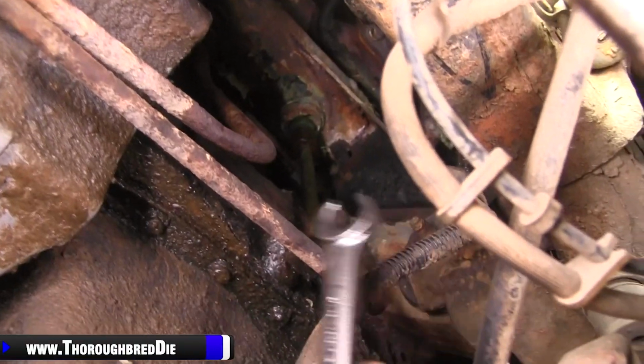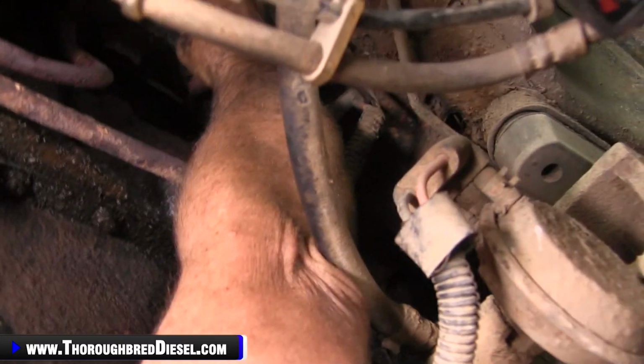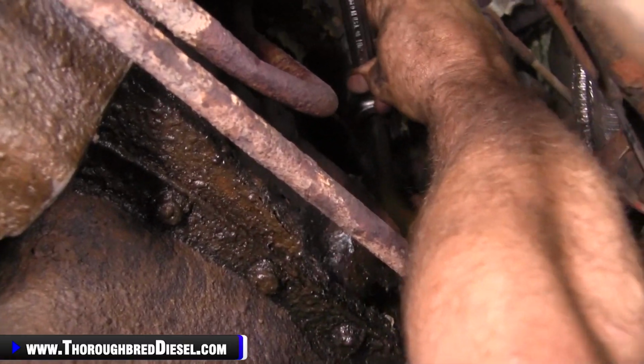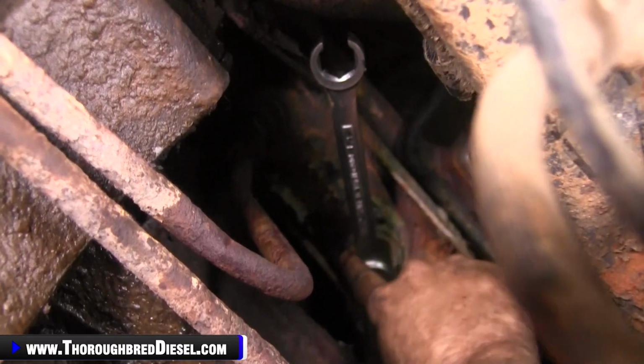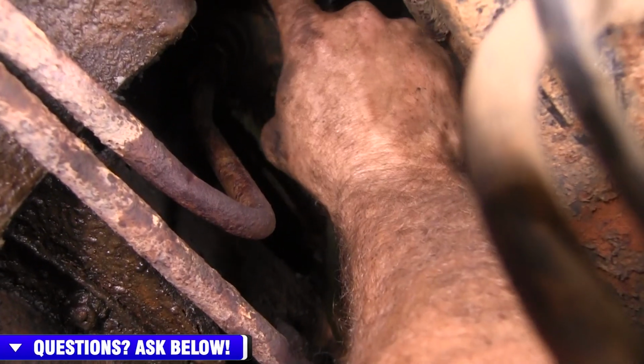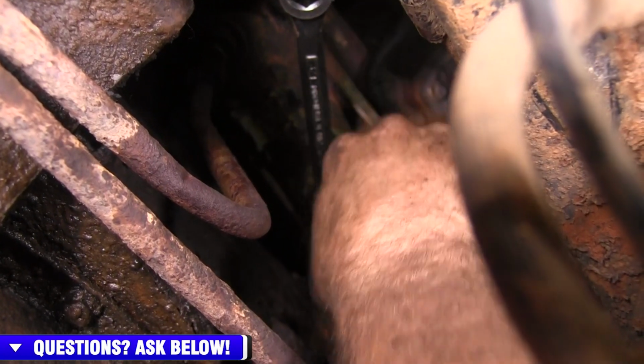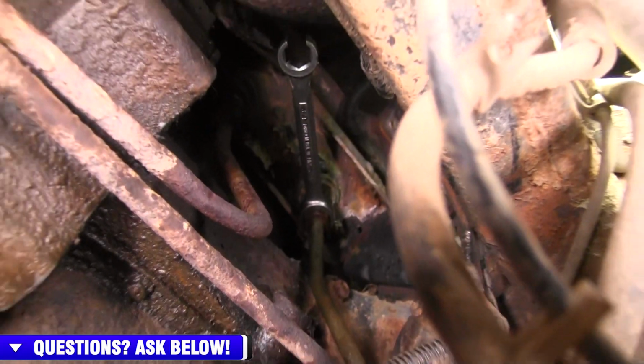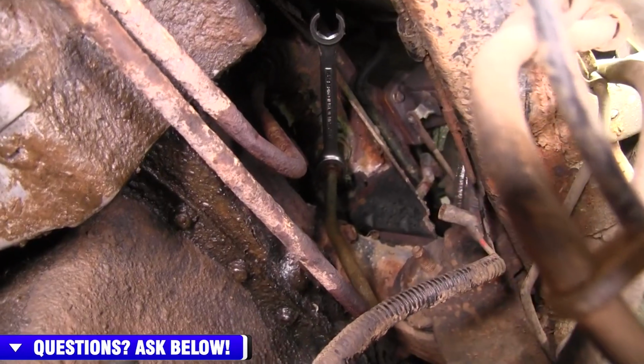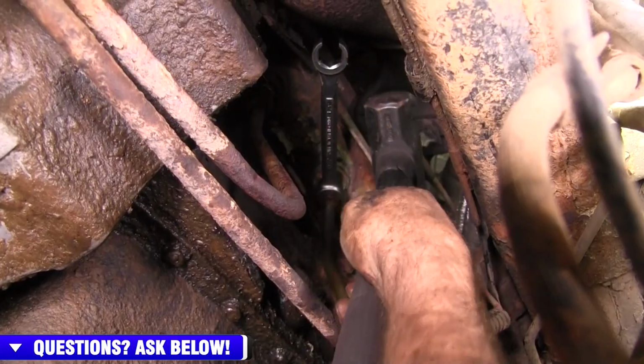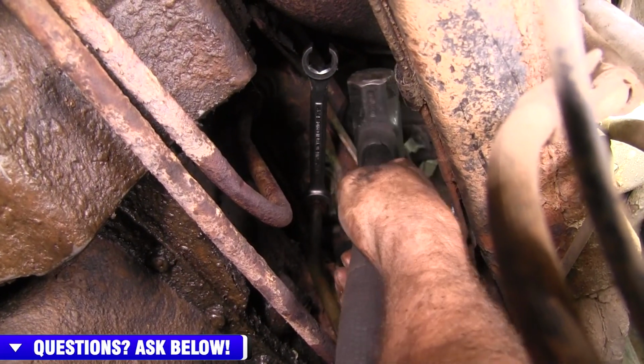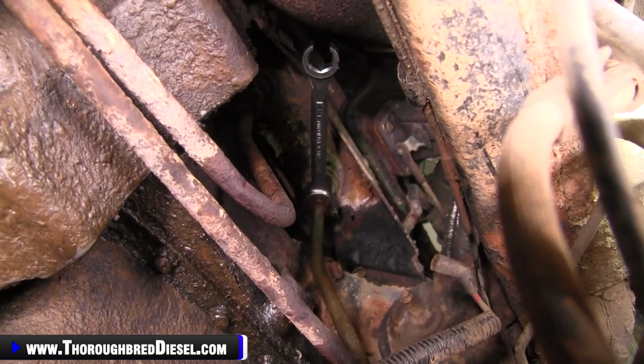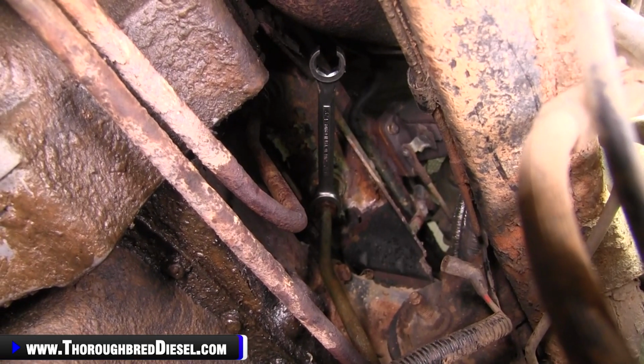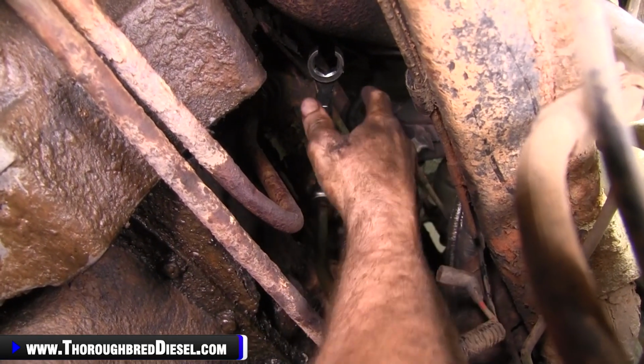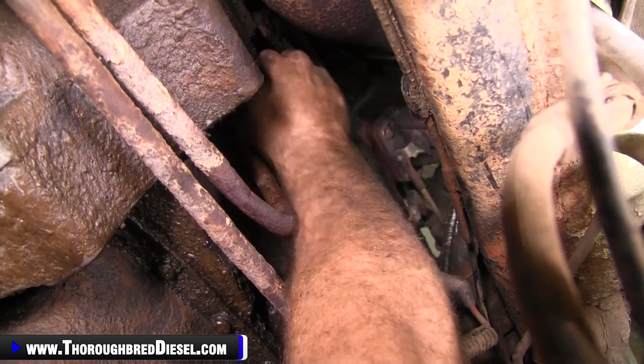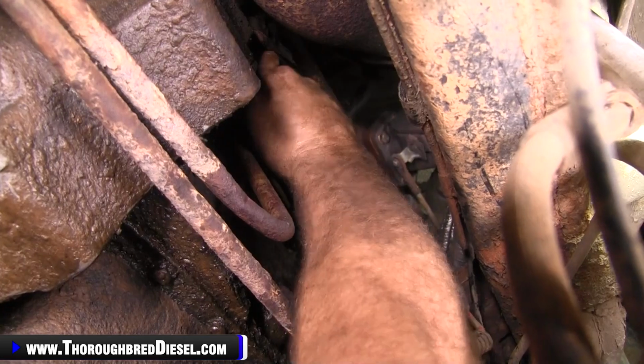These fittings are 7/8, so I take a 7/8 line wrench — usually a bit shorter — and work it onto the fitting. The position of that fitting gave me clearance to get past my downpipe. Then I took a BFH and turned it sideways so I could hit the wrench like that, and that worked it loose perfectly. Not only does that provide enough force to knock it loose at the heat exchanger, it also works some of that corrosion loose.